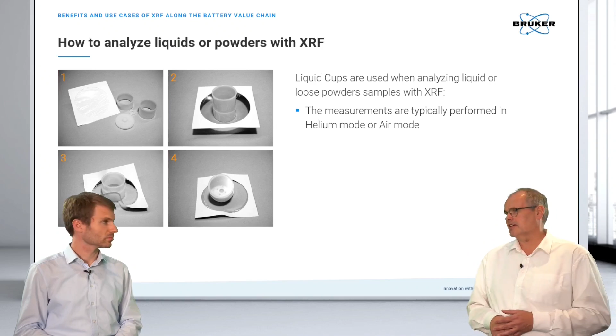Typically, those samples can be analyzed in helium mode for very light elements like sodium and magnesium. In the moment you look for medium or heavy elements like nickel, manganese, cobalt, we can use the air mode, and the intensity is high enough.